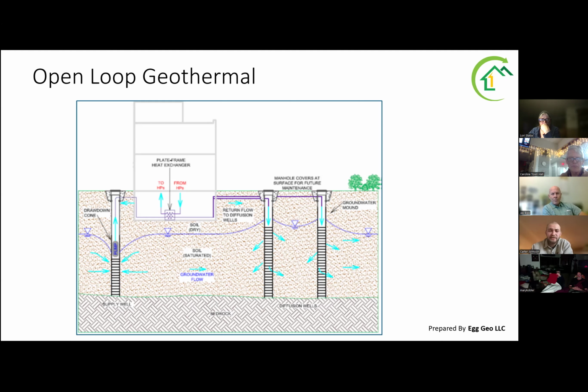There's also maintenance to think about when designing these systems. These open loop systems require being able to get to the wellhead, and require more maintenance. The 70-something wells for the closed loop system, however, require very little, if any, maintenance to the actual wells. You install them, they run to a heat exchanger room, and I believe all the maintenance happens there. Does that sound right, Jay?